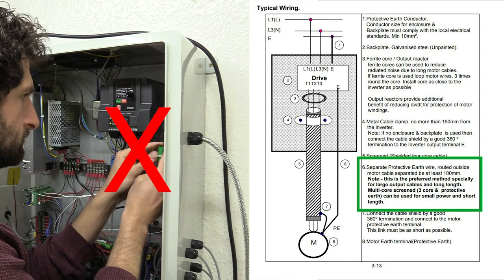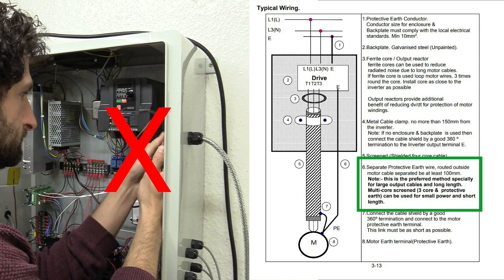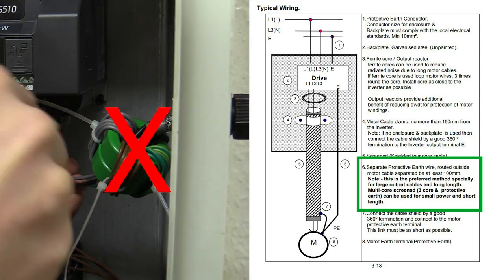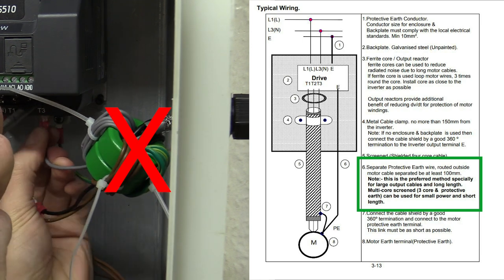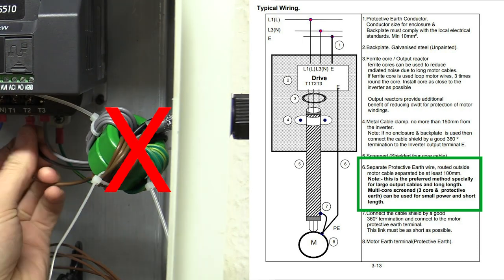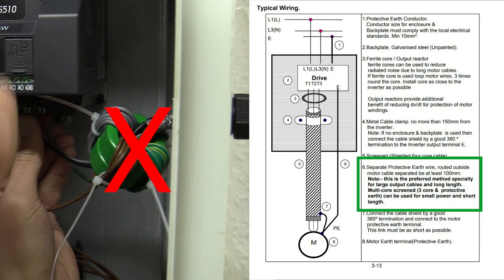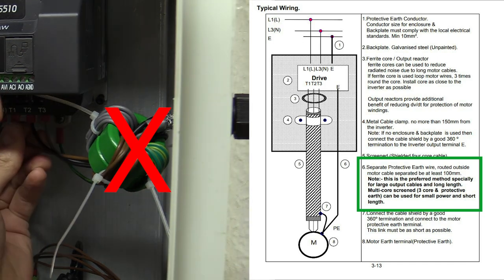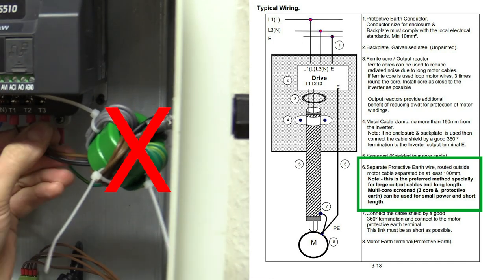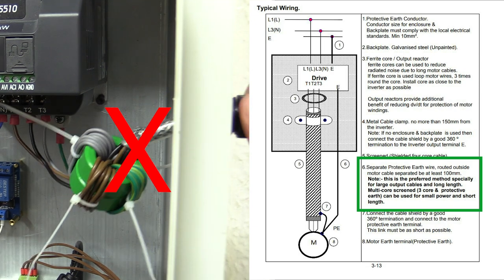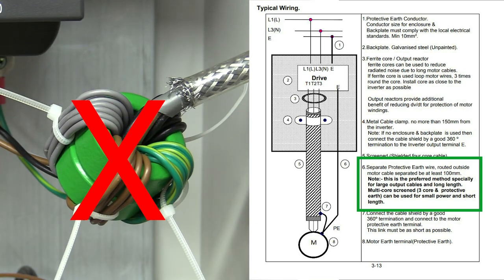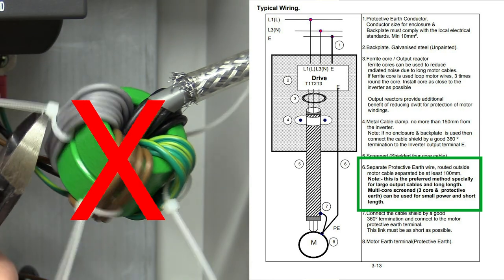I hadn't separated the protective earth cable from the three motor cores. Although it does say, this is the preferred method specially for large output cables and longer length. Multi core screen, 3 core and protective earth can be used for small power and short lengths. So I think using 4 core is ok, but it's not clear what is a large output cable and long length.